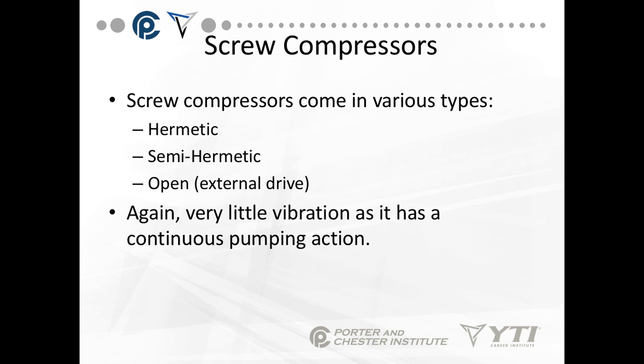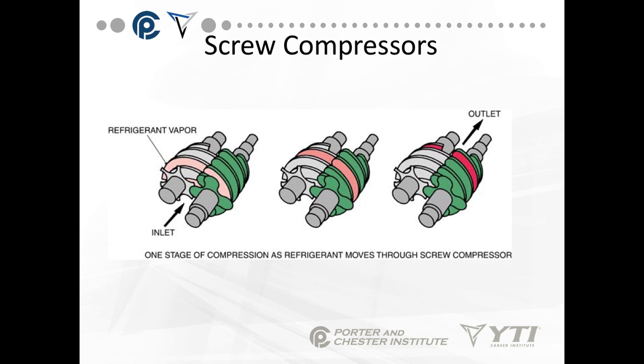Screw compressors come in various types: hermetic, semi-hermetic, and open or external drive. There is very little vibration as there's a continuous pumping action — no back-and-forth action. The refrigerant vapor comes in and is slowly pushed, starting off wide and getting narrower and narrower as the pressure goes up, then comes out the outlet.